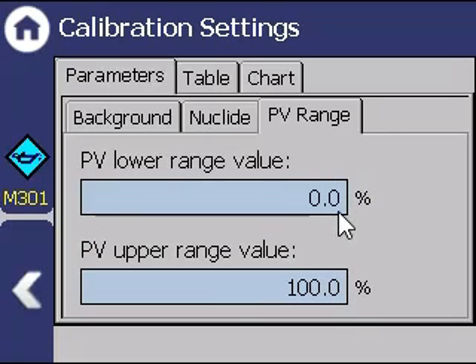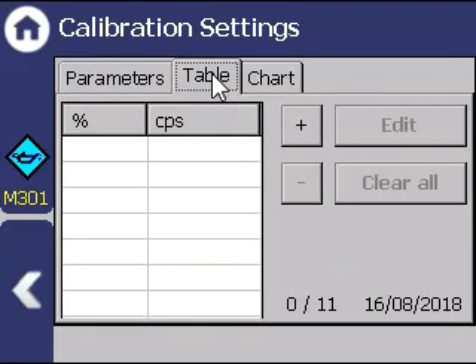If you want a more precise calibration, you will need to get the vessel to the exact 0 and 100% conditions with your product. You can also add points in between for a total not to exceed 11 calibration points. However, you want to have a physical verification of level at each point. Which brings us to the table. You will notice since this is a new setup and there are no calibration points in the table, we can create one by pressing the plus.